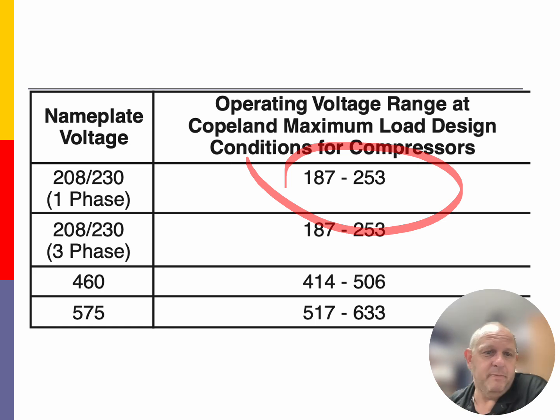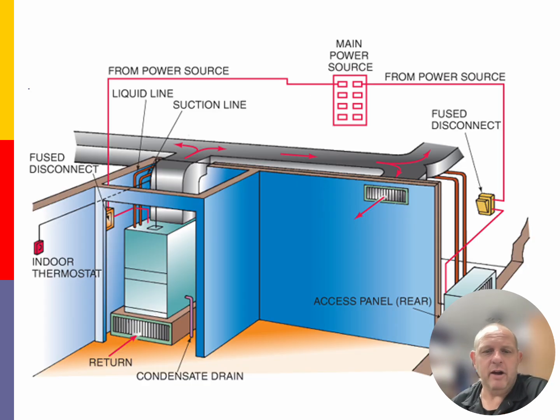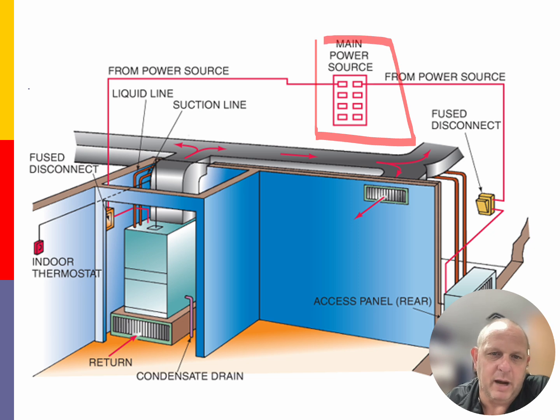Our actual wiring that we're going to be doing for this particular unit is going to be our high voltage. For our high voltage, we're going to be coming into a main breaker box. That main breaker box is going to be fed by a 240 or 120 circuit, depending on what the nomenclature plate says for the indoor unit and the nomenclature plate for the outdoor unit. We'll be running a 240 circuit to the outdoor unit disconnect.